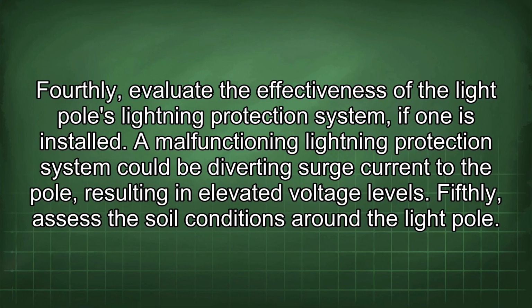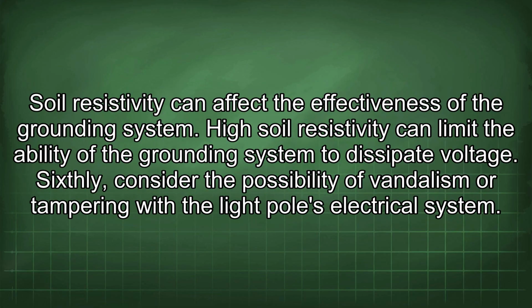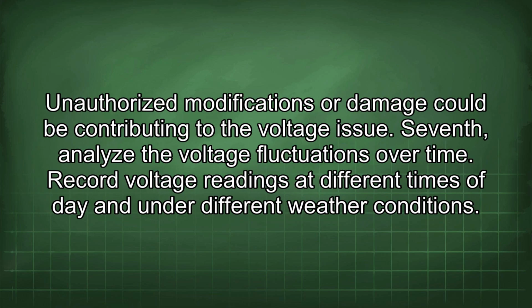Fifthly, assess the soil conditions around the light pole. Soil resistivity can affect the effectiveness of the grounding system. High soil resistivity can limit the ability of the grounding system to dissipate voltage. Sixthly, consider the possibility of vandalism or tampering with the light pole's electrical system. Unauthorized modifications or damage could be contributing to the voltage issue.